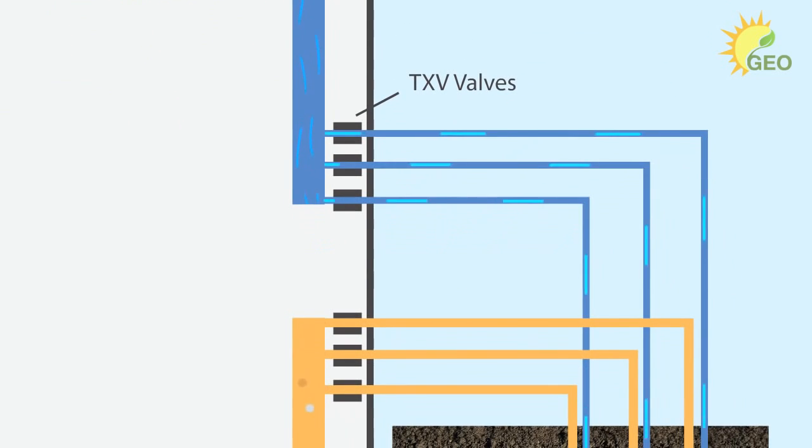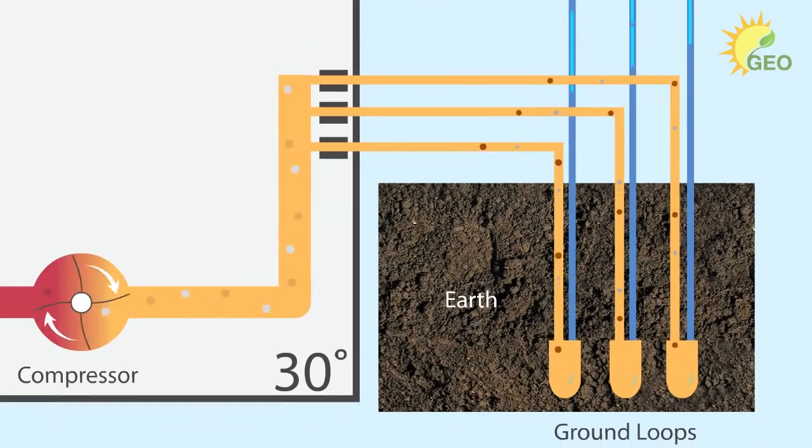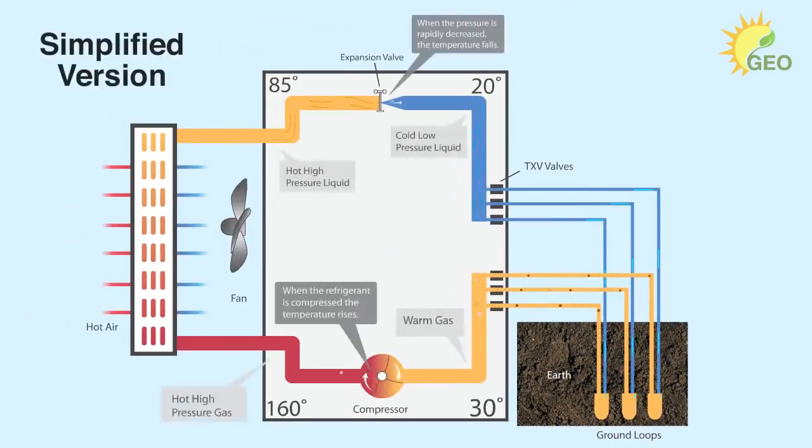It then moves toward the TXV valves. These valves control the amount of refrigerant distributed to each ground loop. The refrigerant is then piped out to the wellfield and down the vertical boreholes where it begins its transformation back to a gas. As it transitions back to its gaseous state, it absorbs heat energy from the earth and travels back to the compressor where this ingenious process is repeated.